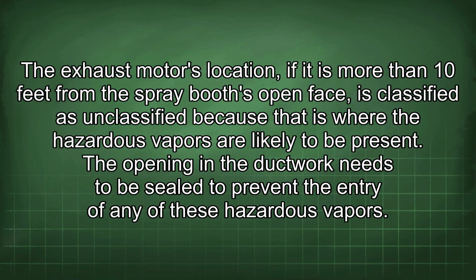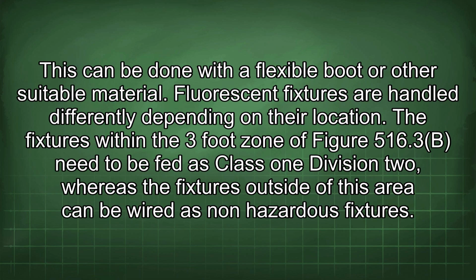The exhaust motor's location, if it is more than 10 feet from the spray booth's open face, is classified as unclassified because that is where the hazardous vapors are likely to be present. The opening in the ductwork needs to be sealed to prevent the entry of any of these hazardous vapors. This can be done with a flexible boot or other suitable material.